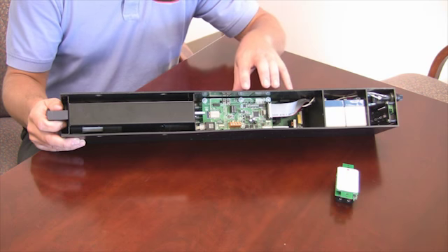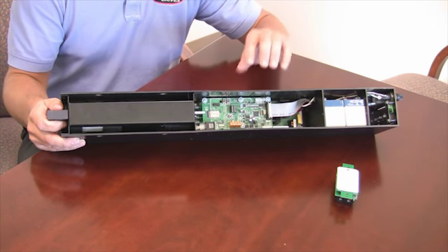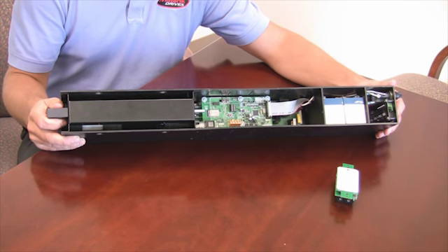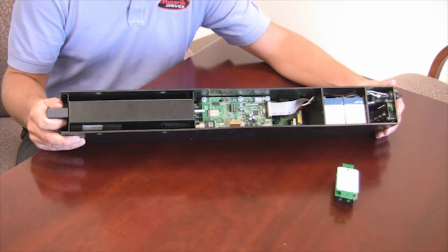The drive itself has about 15 I/O, including an encoder input, a 2-channel optical input, 2 Modbus ports, a motion sensor, both wired and wireless, clutch output, brake output, and 10 channels of remote control, 5 of which are wired and 5 of which are wireless.